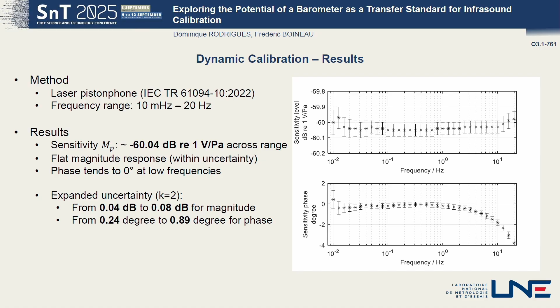Okay, here are the results for the dynamic method. We used the laser pistonphone. It was calibrated in the frequency range of 10 millihertz to 20 hertz. So you have the results here in amplitude and in phase. As expected, the frequency response is relatively flat, with an average value for the sensitivity close to minus 60.04 dB, and the phase tends toward 0 at low frequencies, also as expected. And you can see here the typical uncertainties that we can reach with such a method. The larger uncertainties are typically achieved at the lower frequencies.